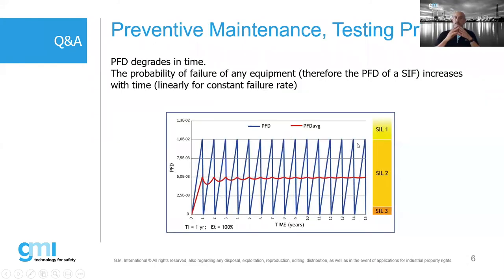As preventive maintenance, maybe you ask for the proof testing. And if you are using a SIL power supply or a SIL device, the manufacturer has to deliver to you also the safety manual with all details about the proof testing. So once you have the product that is certified for a certain SIL level, if you want to keep that level for a long time, you have to maintain and test the device after a certain period. And in the manual, there are all details about the proof testing that is really required on your system, on your applications. Let's try to answer live some questions you posed.